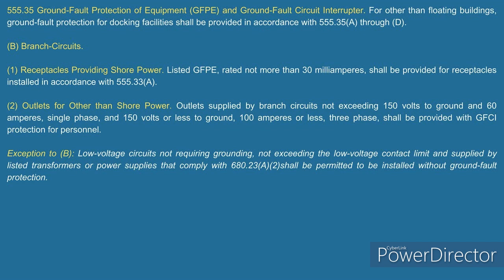And that's why I say this also. If it is the case, like he's saying, right there where it receives its supply, there would be no need to have a definition for a receptacle outlet, because you've already stated that the receptacle is where I'm picking my point up, not at the outlet but at the receptacle, which is a device. And if I'm hitting a device, that is where I'm cord and plug connecting, and I have personnel that has interaction at that point around a wet location. If it's hardwired, the personnel doesn't have any type of interaction with it. Yep, I agree.